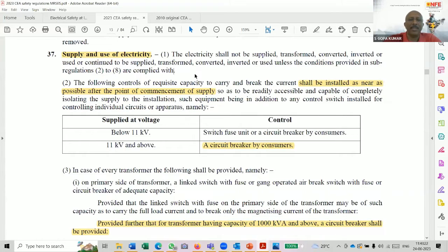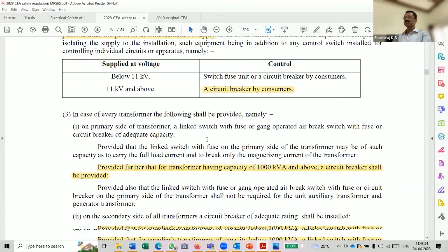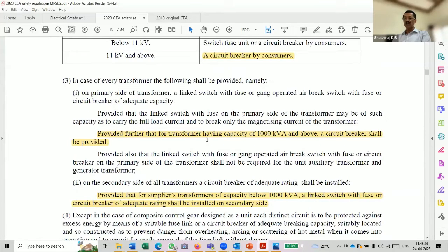Every transformer, they are required to provide a breaker, which was not provided earlier because most of the stations were without breakers, and there were a lot of accidents and station interruptions also. So now we have made it very clear and very sure for them that they have to get the drawings approved, and we will issue an approval before charging, and that is recorded.